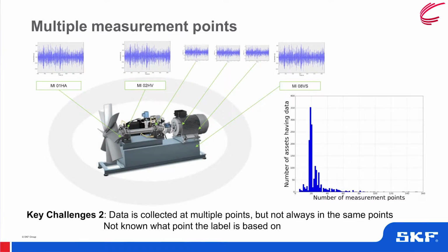Okay, let's now move on to the second challenge, not just the limited amount of data. It's also about the nature of the data itself. Because when we talk about heavy assets, you take the vibration measurements, it's not a single location. It's actually multiple locations. For each asset, you actually have multiple measurement points. Here you have 6 measurement points, so each time you have about 6 of these waveforms.